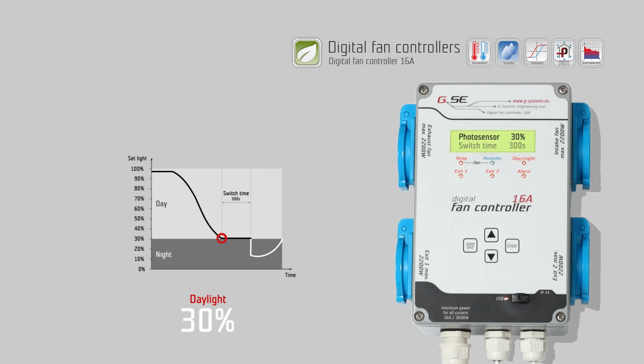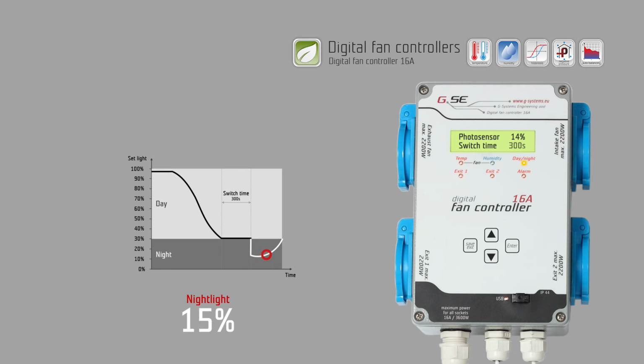Scroll down. Select Switch Time, and press Enter. The switching time is a time delay which starts a countdown after reaching the light sensor level. This function is used to prevent an immediate alternation if you momentarily failed to shield the device from light, like from the brief opening of a door. Set the desired value and press Save Exit.